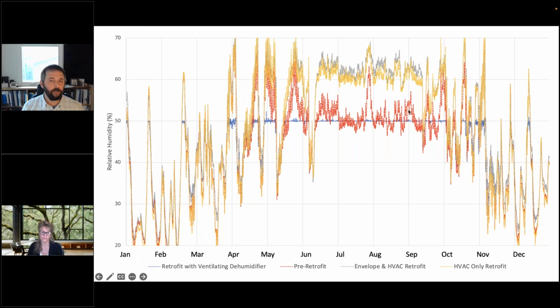The results show the original pre-retrofit home was able to maintain around 50% RH in summer. Now that we've done this energy retrofit, reducing the sensible load of the structure, we may have added a little bit of latent load, but disproportionately, so we're seeing less AC runtime. We've also potentially reduced the system's capability to remove moisture by using a very efficient sensible-removal machine.